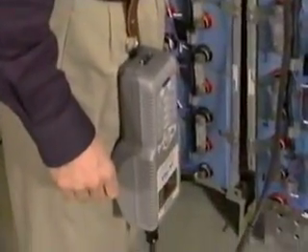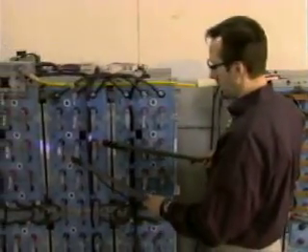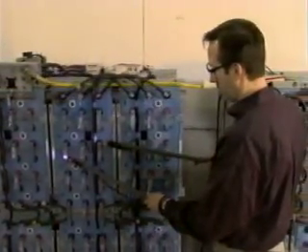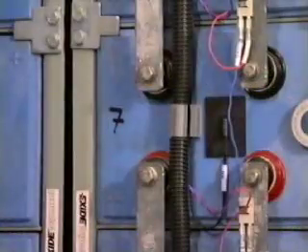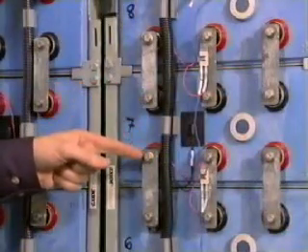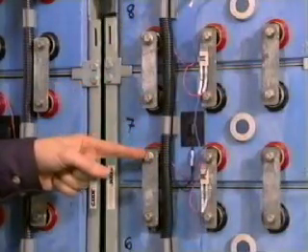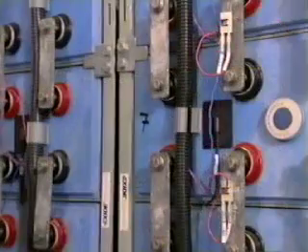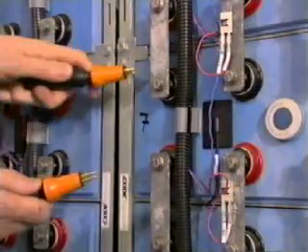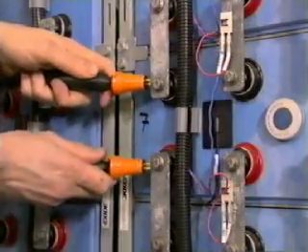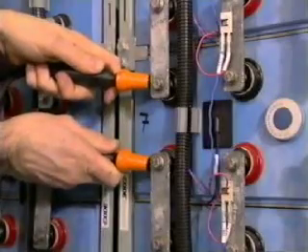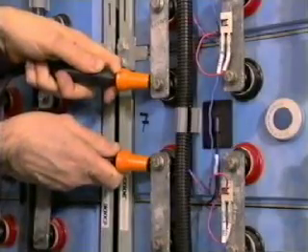Let's start with the DuraProbes. It's important to understand where the best contact points are. One contact point to avoid is the stainless steel hardware. Stainless steel gives higher test readings, possibly even a false failure indication. Instead, make sure the probe touches directly onto the lead post. This registers the lowest measurement and the most uniform information.